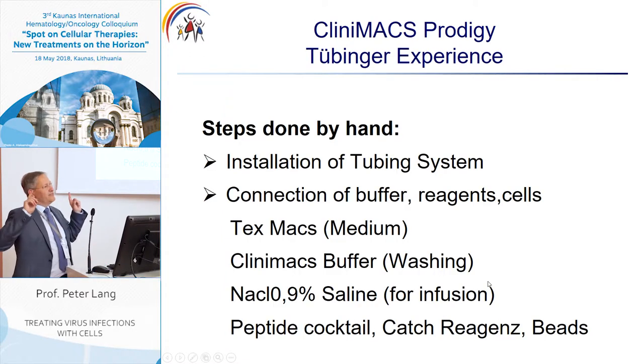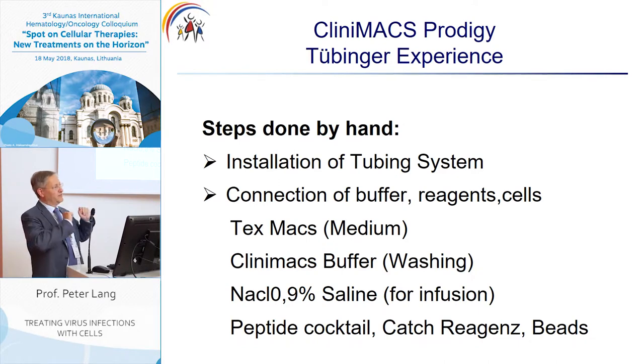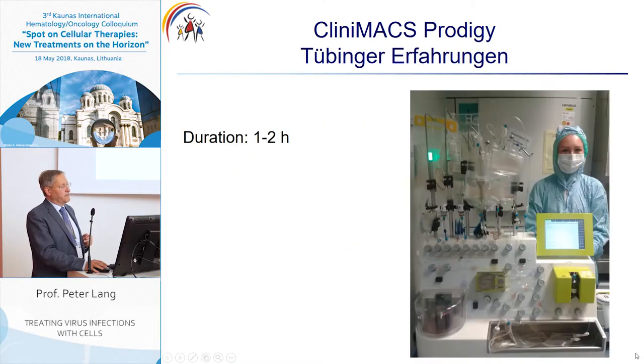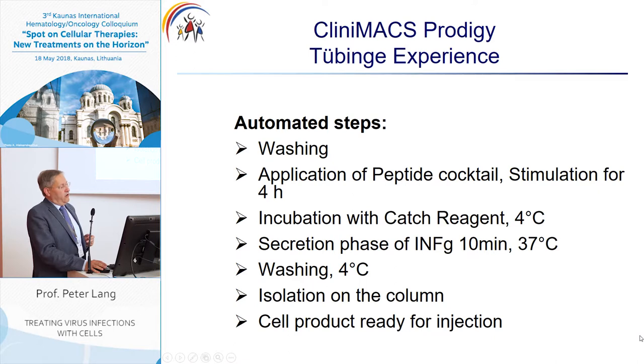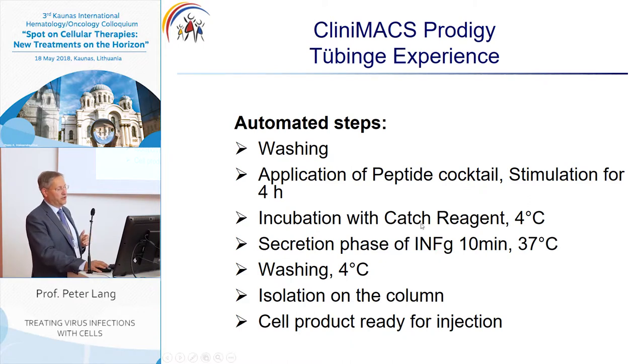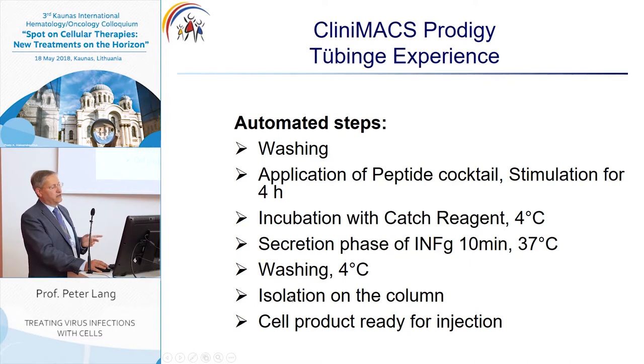The Prodigy is an almost fully automated device, but a few steps must be done by hand: installing the tubing set, connecting buffer reagents and cells, adding medium, washing buffer, saline for infusion, peptide cocktail, catch reagents, and beads. This setup needs one to two hours. All other steps are automated, including washing procedures, application of the peptide cocktail during the night, stimulation for four hours, incubation with the catch reagent at four degrees, the secretion phase of interferon gamma at 37 degrees, cooling and washing, the isolation run on the column, and finally the cell product is ready for injection.